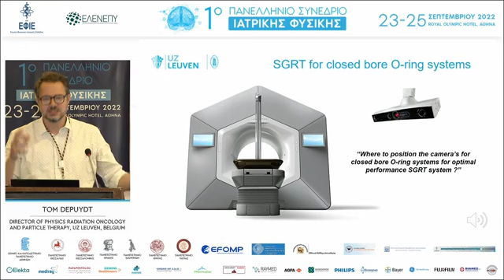First of all, where do you put these cameras? Because we're used to a C-arm, a more open structure of a linear accelerator, while now it's like a closed bore system. Where do you put these cameras? What's the optimal position of these cameras? If you look at a Halcyon system, the isocenter is marked here in red, so it's inside the system. And a difficulty with that position is that in isocenter, you do not have access to the patient. So the RTTs, if they have to move the patient a little, or there's a little roll or whatever, or the arm is not right, arms might not be a big issue, but for some other rotations, you basically don't have access inside the bore to the patient. And that makes it really difficult.